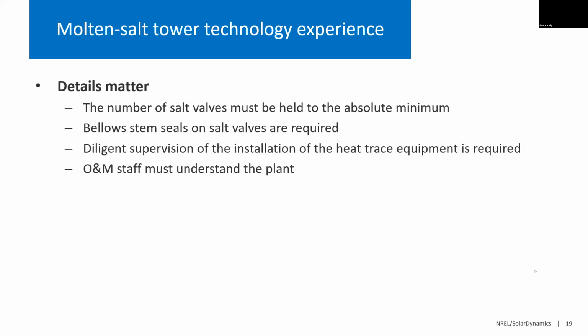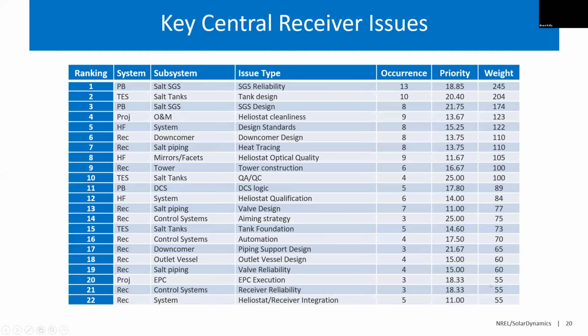And also, the O&M staff has to understand the plant. These plants operate with high temperatures. They also operate with high temperature differentials. And it's possible to damage equipment very easily if you don't maintain strict control over what flows are going when. The best way to ensure that is to make sure that the O&M staff understands how the plant runs, and how to protect the plant from damaging conditions.